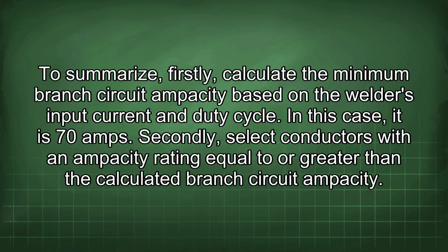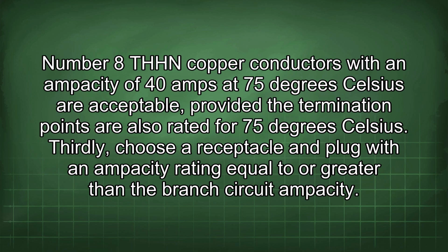To summarize, firstly, calculate the minimum branch circuit ampacity based on the welder's input current and duty cycle. In this case, it is 70 amps. Secondly, select conductors with an ampacity rating equal to or greater than the calculated branch circuit ampacity. Number 8 THHN copper conductors with an ampacity of 40 amps at 75 degrees Celsius are acceptable, provided the termination points are also rated for 75 degrees Celsius.